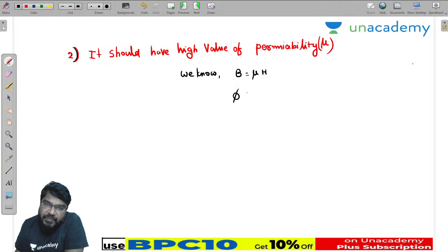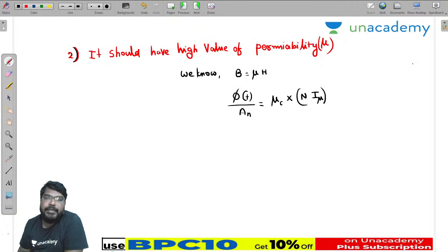Therefore, flux phi of t divided by the net cross sectional area of the transformer core equals the permeability of the core multiplied by H. Here H is directly the number of turns multiplied by the magnetizing current of the transformer, divided by the length of the core. So H equals number of turns times magnetizing current divided by length of the core, that is the magnetizing force.